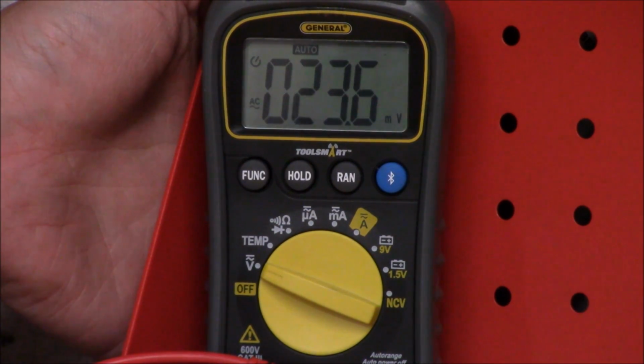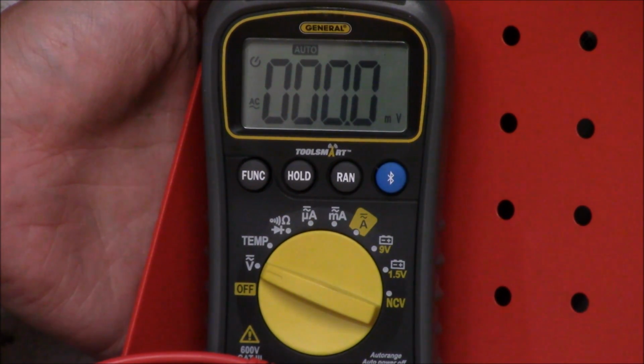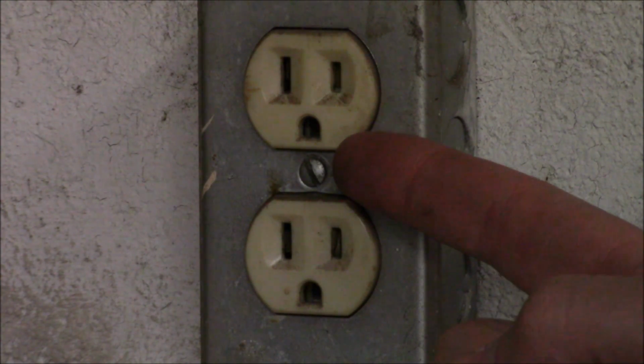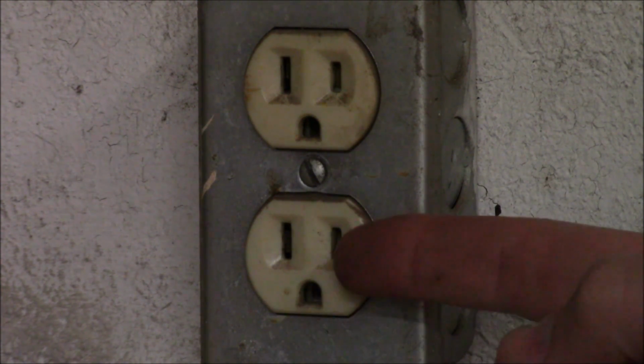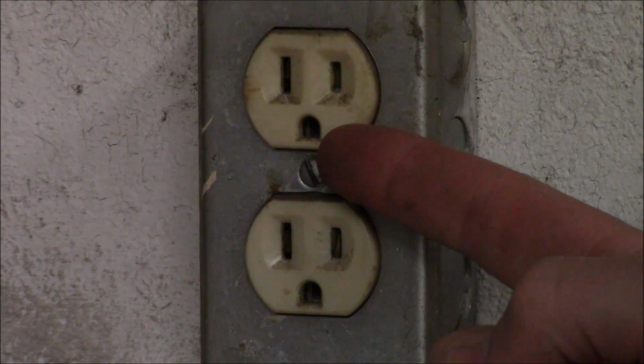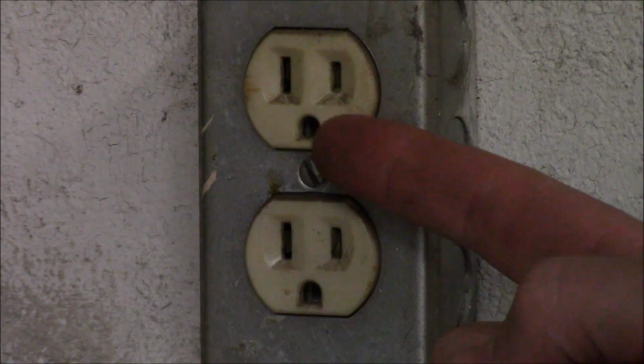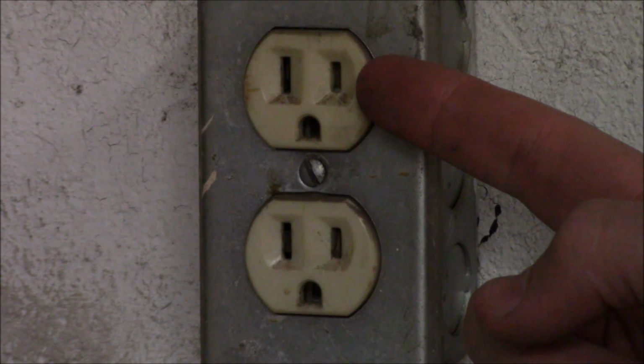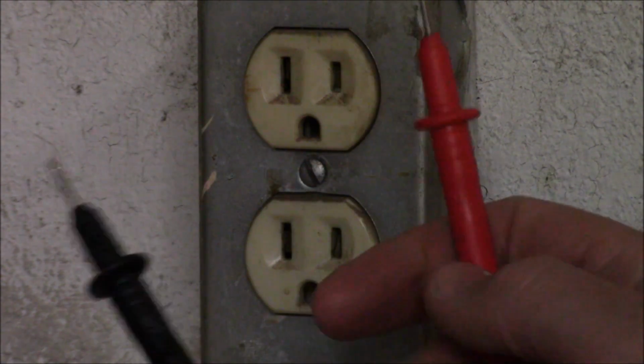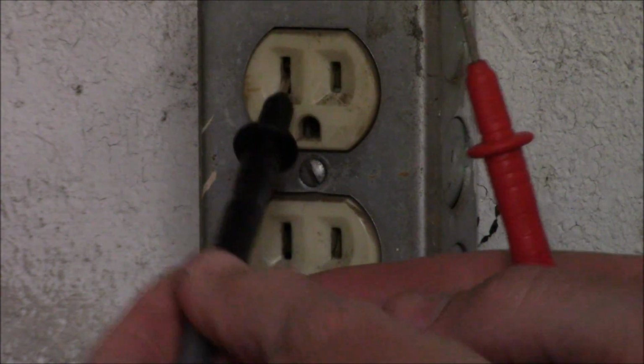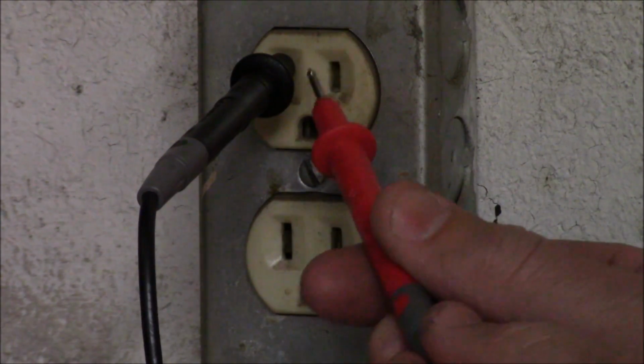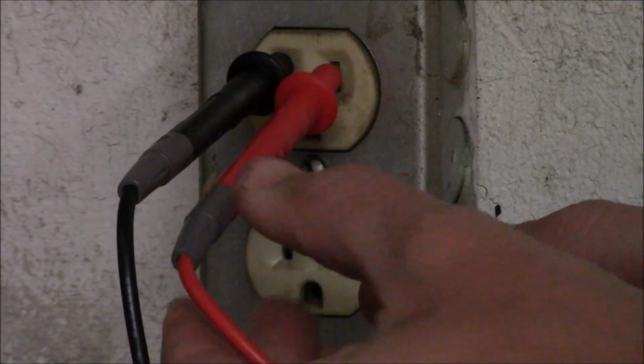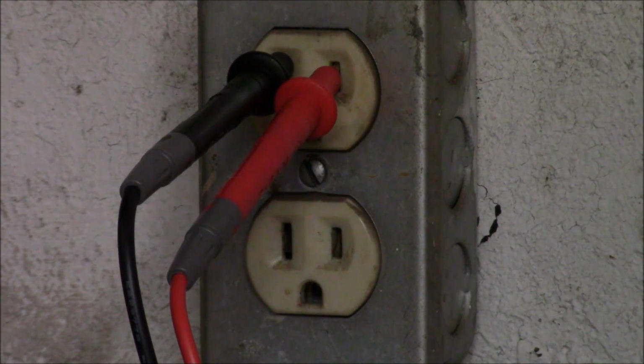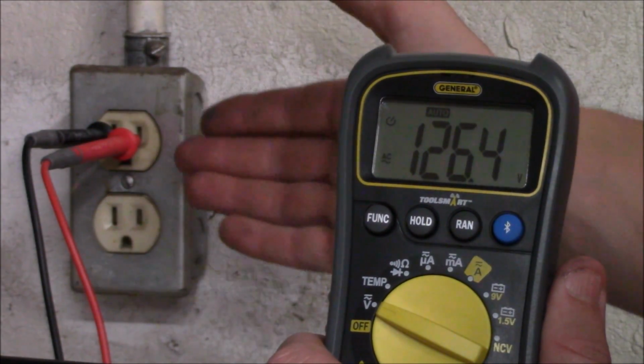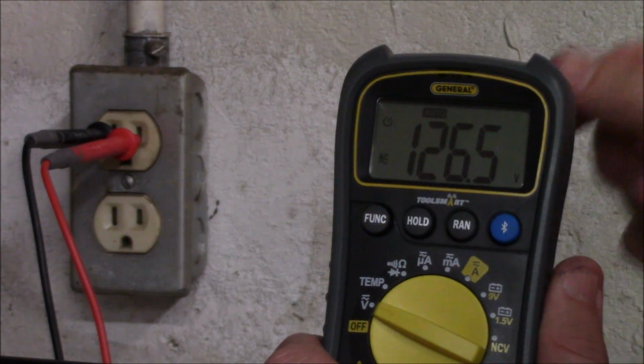At this point we can take our 2 leads and measure the voltage in the wall. A standard wall outlet looks like this, with 3 different holes: the round one on the bottom is the ground wire, the large one on the left is the neutral wire, and the small one on the right is the hot wire. We'll take the black lead and put that in the neutral side, and the red lead into the hot side, then look at our meter to see the reading at this outlet, which shows standard wall power coming in at roughly 126.4 volts.